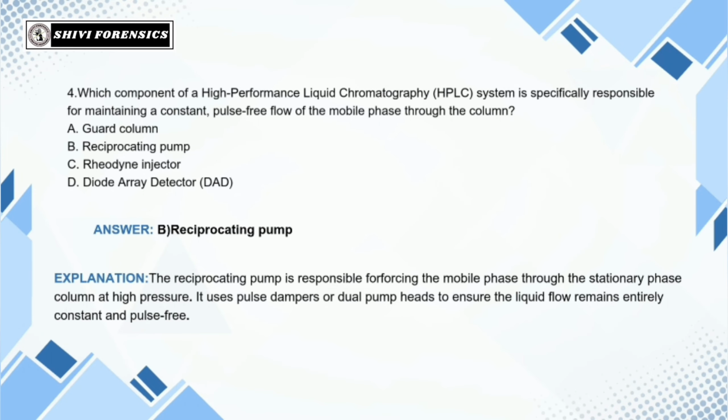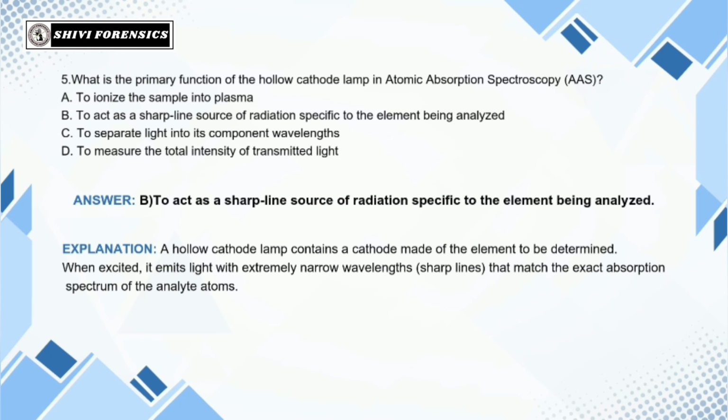Fourth question. Which component of a high-performance liquid chromatography system is specifically responsible for maintaining a constant pulse-free flow of the mobile phase through the column? And the answer is reciprocating pump. The reciprocating pump is responsible for pushing the mobile phase through the stationary phase column at high pressure.